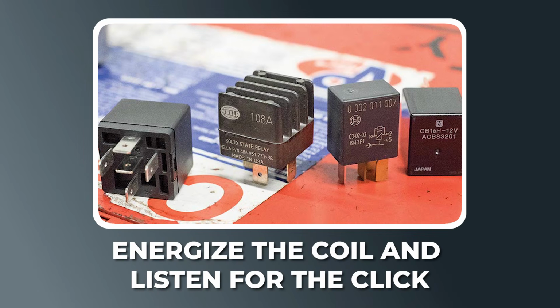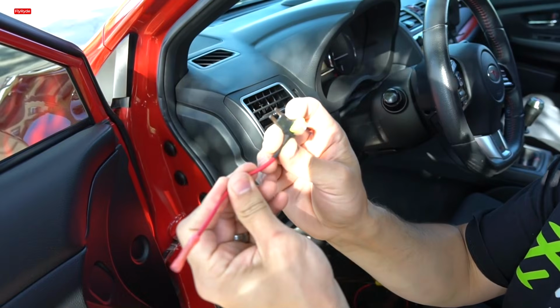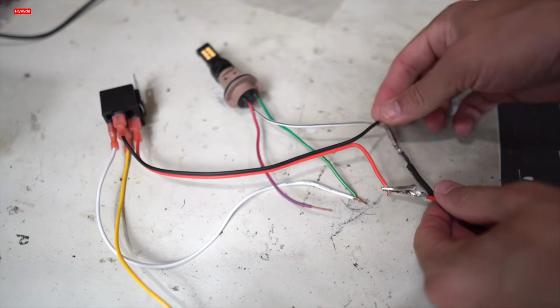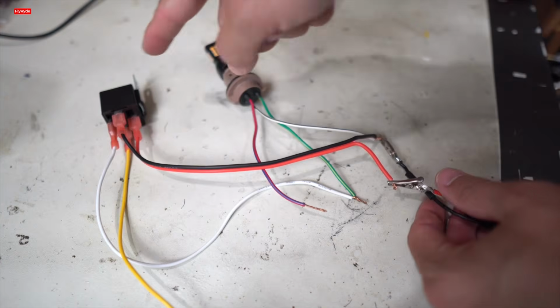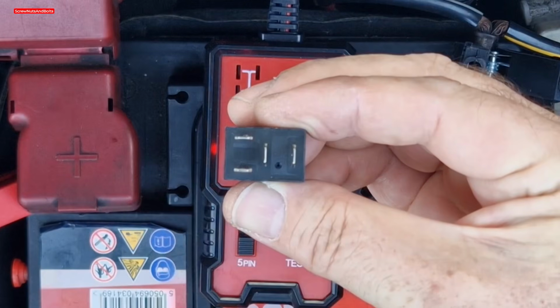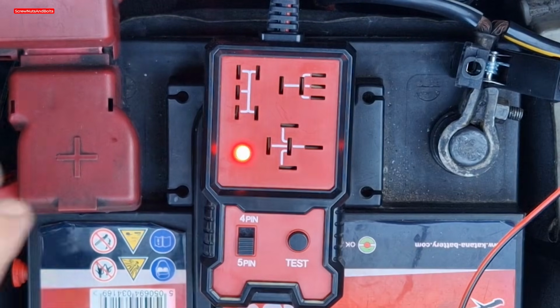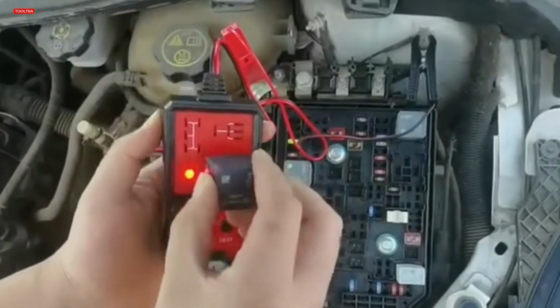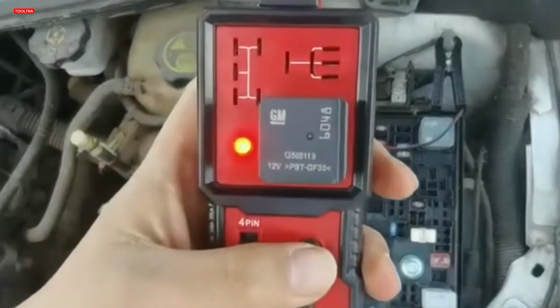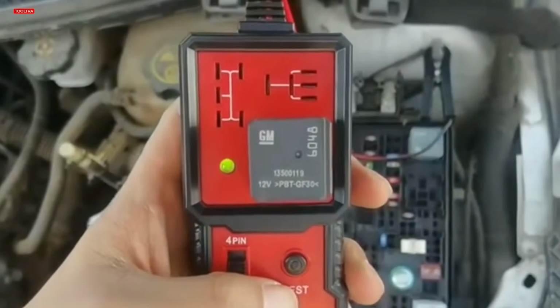Energize the coil and listen for the click. This is the test that tells you the most. Apply power to the coil pins and the relay should snap audibly. No click means the coil is not pulling the armature. A weak or hesitant click often means a failing coil that works cold and fails when hot.